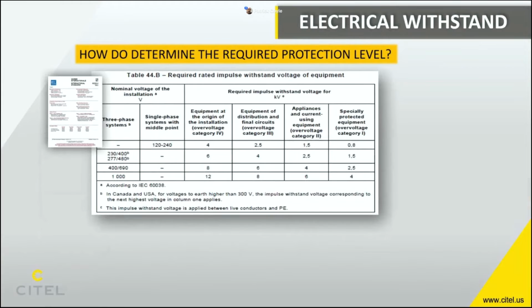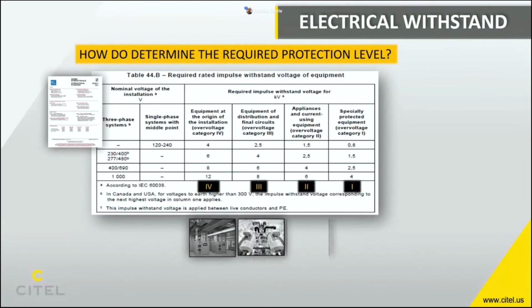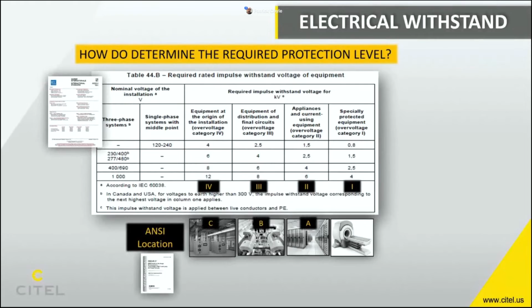So we can start with the standards again. We can look at the IEC 60364-4, and there's a table 44B. So it describes the rated impulse withstand voltage of equipment based on the location in the building. So 4 is the equipment at the front of the building, and 1 is deeper in the building, usually in specialized rooms. We can also look at the ANSI C62 series for a North American equivalent.